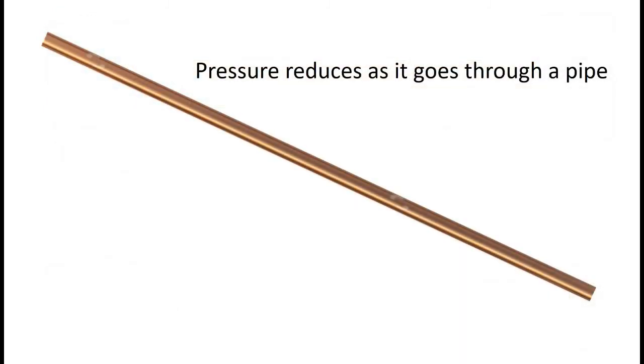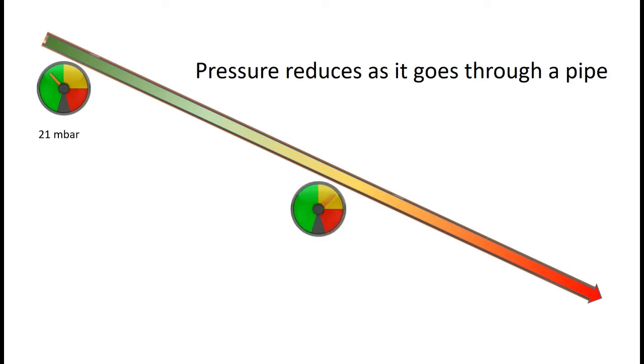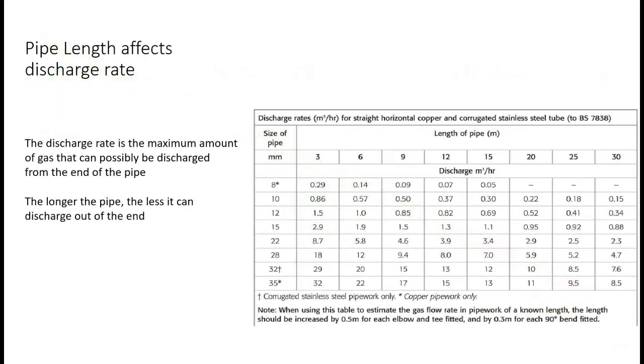Now pressure reduces as it goes through a pipe. It might start at the beginning of a pipe at 21 millibar. As it travels through it loses pressure, perhaps down to 20, and then by the time it comes out the end of the pipe it might only be 19 millibar. This pressure loss is what we are having to take account of when we do our pipe sizing. This has already been worked out in the discharge tables.